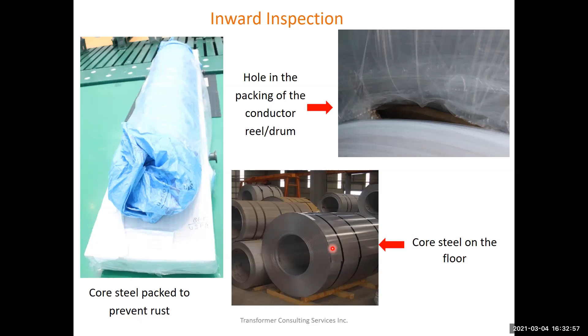The question comes, where are these metal particles coming from in this factory that can compromise the quality of the transformer? If you look very carefully at the roof of the factory, they have a crane which has not been maintained properly and is running back and forth quite frequently to haul all those big transformers. Those gears are wearing out and creating iron filings, which are going to land inside the transformer and can cause the failure of the transformer in the long run.